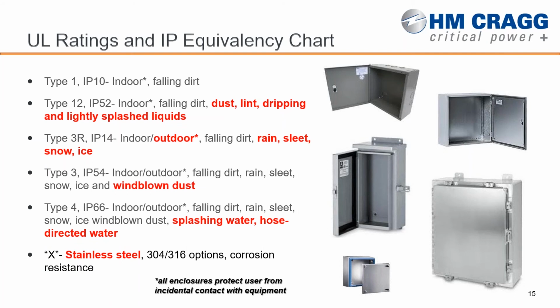The type 1, that's what most enclosures in a regulated indoor environment would be. An IT enclosure, a 2 or 4-post rack sitting in a network closet or in a data center, that would be a type 1 enclosure, fully vented. Anything in the atmosphere would get through it and into the equipment that's inside. But what does it do? It does two things. It protects the user from incidental contact with whatever's inside, because with the doors closed and the sidewalls on, you can't touch the equipment, the front or the back. So there's that level of protection. But the other thing it'll do is protect against falling dirt, like from the ceiling or something like that. It will protect the equipment from anything that may be coming from overhead. So that's type 1, the least level of protection, but for an indoor, well-regulated environment, that's the rack that we're most used to, I guess.